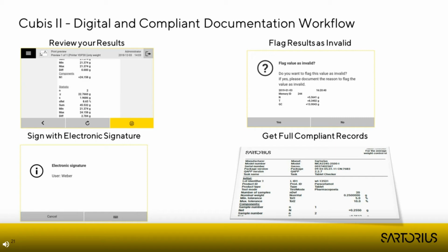the balance touch screen. So when you have reviewed your results and made your corrections, then you can directly sign it on the balance with your electronic signature as creator. This is very useful for you because you don't have to go to the PC. It can be directly signed on the balance screen, and then you can continue your work directly without switching between PC and the balance.